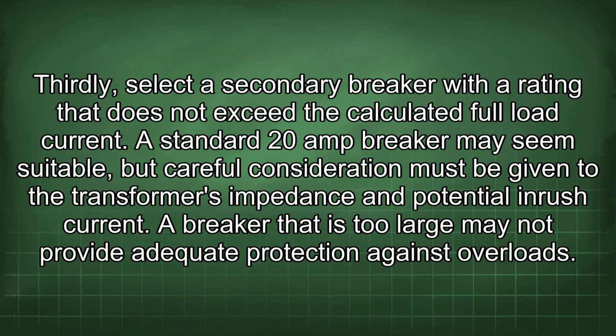Thirdly, select a secondary breaker with a rating that does not exceed the calculated full load current. A standard 20 amp breaker may seem suitable, but careful consideration must be given to the transformer's impedance and potential inrush current. A breaker that is too large may not provide adequate protection against overloads.